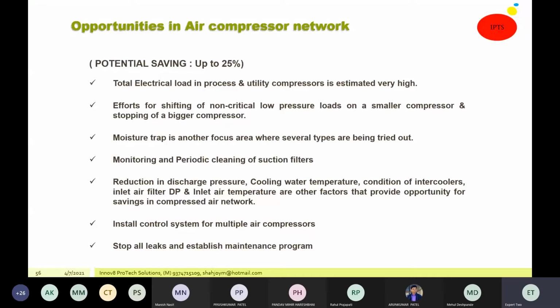This is one area because if you see any of the industry, you will find multi-stage compressors, the intermediate stage knockout drum, continuous air venting taking place. So you can look at using a moisture trap. You can look at cleaning of the suction filter so that energy consumption is reduced. You can also look at reducing your discharge pressure based on the requirement, and install a control system for multiple air compressors. And ultimately, leakage is the major enemy of compressed air energy consumption, and a proper maintenance program should be there. So whenever you go to the industry, try to find out what more you can do so that energy consumption can be reduced.